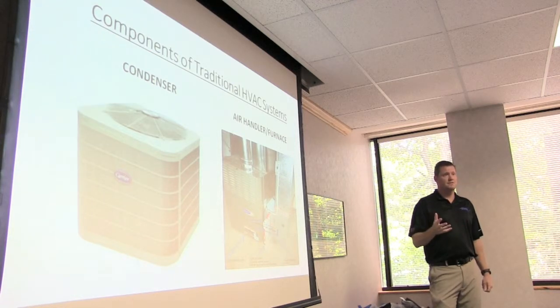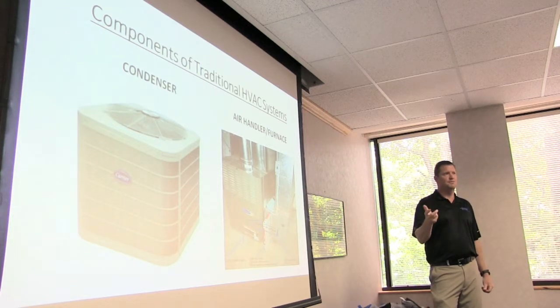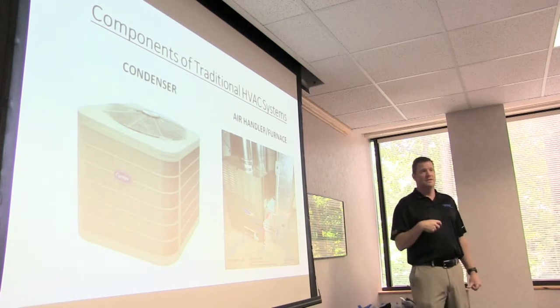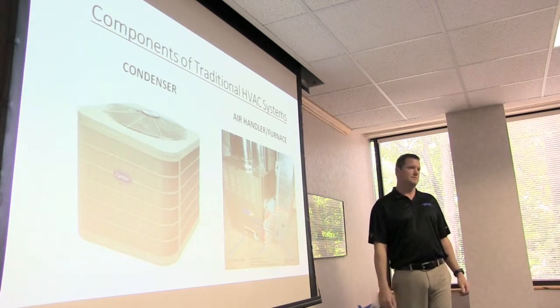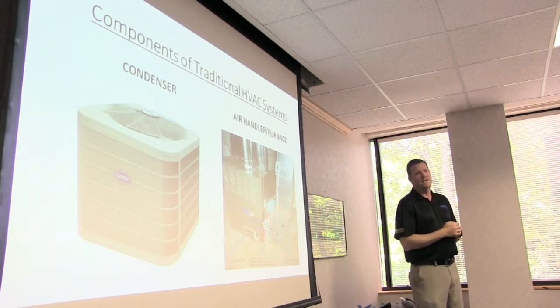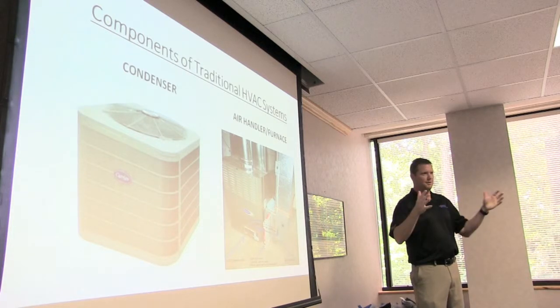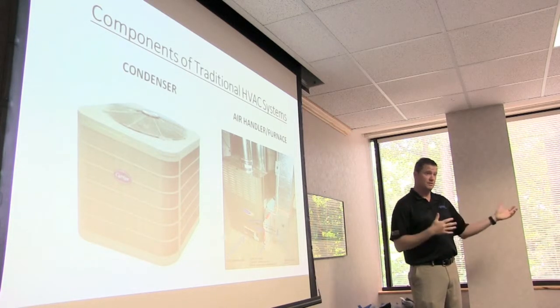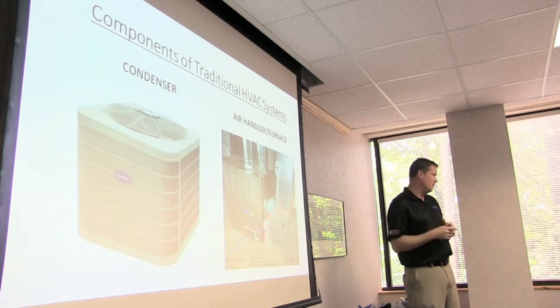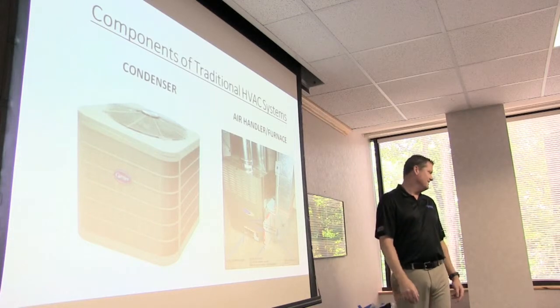There are a lot of heat pumps in this area also. This is about as far north as you can go with a heat pump, because the heat pump actually draws heat from the outside air. So below about 30 degrees, they're horrible, absolutely horrible. They're only good for AC. South Carolina is really as far north as you should go with a heat pump. But some of the builders put them up here because they're inexpensive. You don't need two separate units, it's all in one. So when it gets below 28, it doesn't work anymore.